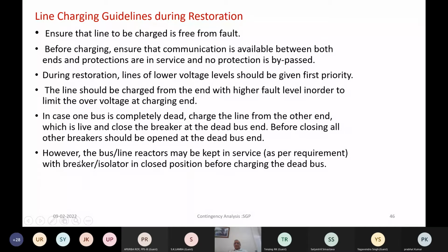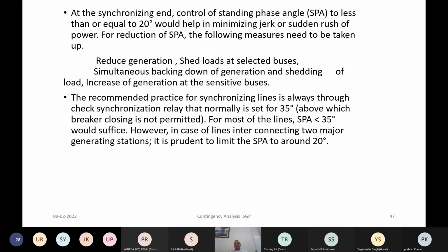Then the bus or line reactors may be kept in service as per the requirement with a breaker or isolator in closed position before charging the dead bus. If there are long lines, then to control over voltages, we should have reactors all lined up so that over voltage can be controlled after charging. Likewise, there are procedures given.